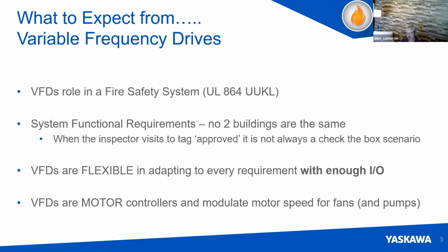We'll talk about system function requirements. And the most important thing to learn today is that whatever it is that you're trying to do, whatever the inspector wants from your installation, VFDs in general are flexible enough to almost meet every requirement. It's just enough IO being on board on the drive, and then being able to program that drive so that it can do what is expected.